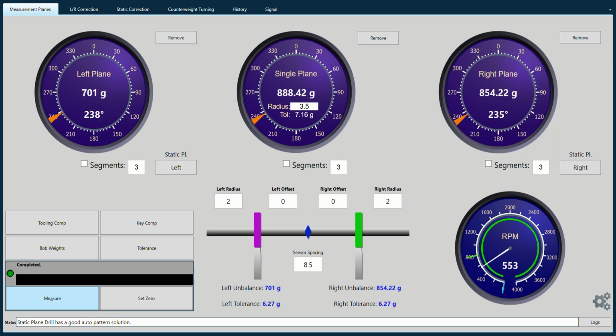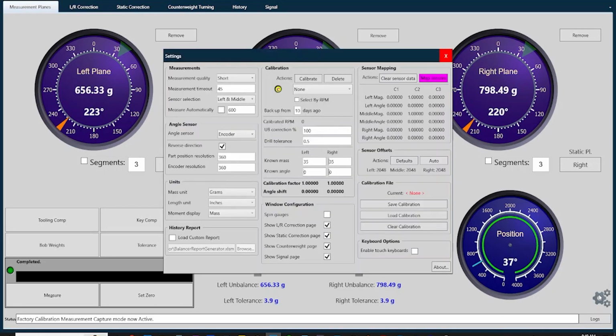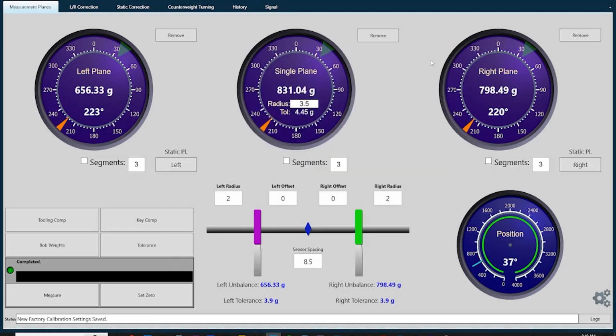After taking the highest speed reading, press the gears icon again and press Map Sensors once more. This will close out the procedure and set the curve for your sensors, ensuring consistent angle readings between those speeds. After completing the sensor mapping, you're ready to calibrate.